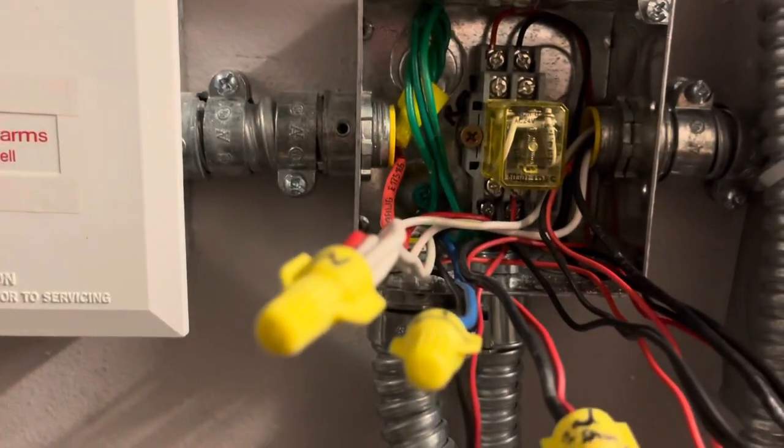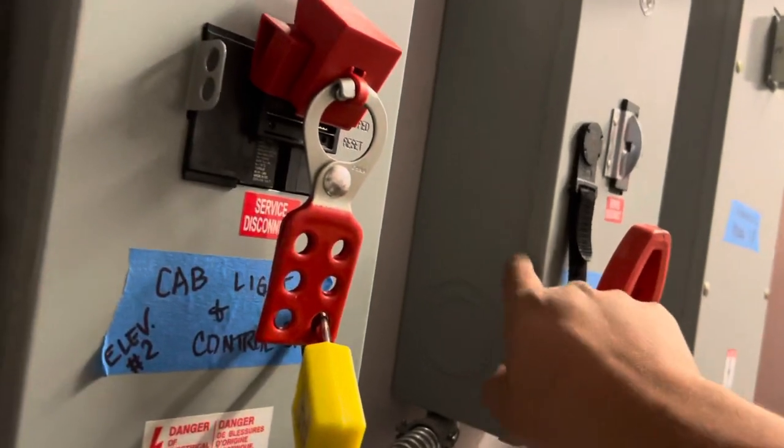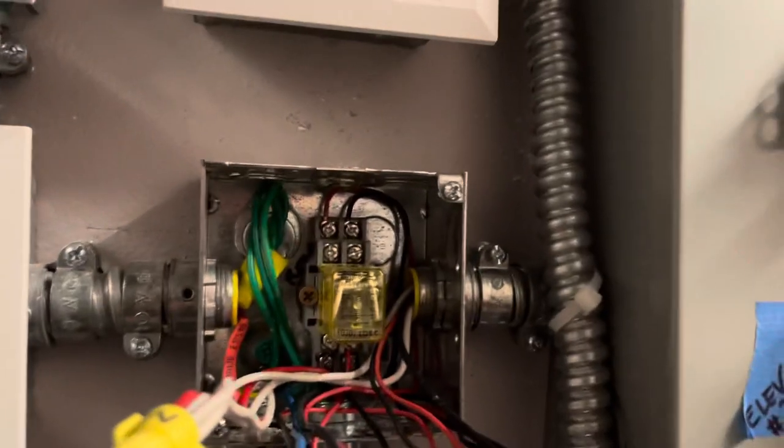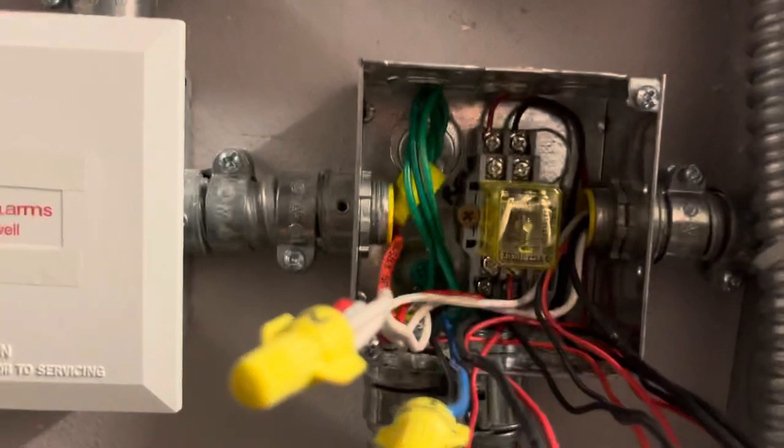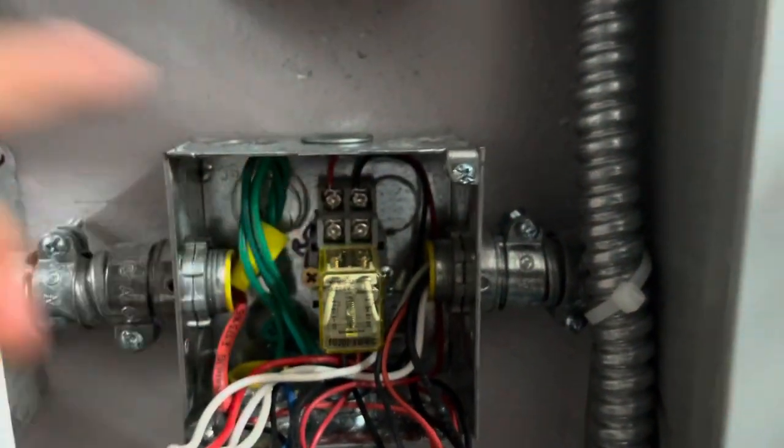And then now talking about your 120 power. So this is a 120 shunt, so I need 120 to shunt or create a direct short on this guy right here. So to accomplish that, you basically go from the neutral side of your shunt. All your neutrals will connect right here into one bundle. There's no need for them to go on to this.